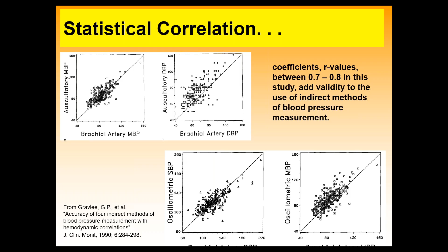The oscillometric method, you've seen these things around also, even in the grocery stores, Walgreens, they'll have these things in there. This is also an indirect method, also giving us an estimate. The main benefits of this machine, obviously, is that it's not using a stethoscope, for one, and it also controls the inflation and the deflation rates very precisely to eliminate another source of variability that way. And it still produces the same vibrations in the cuff, same Korotkoff sounds, but now those vibrations are transmitted to the cuff as pressure fluctuations. So the machine is actually picking up pressure fluctuations here, and it's from those pressure fluctuations and their magnitudes that the machine will derive and display systolic, diastolic pressures.